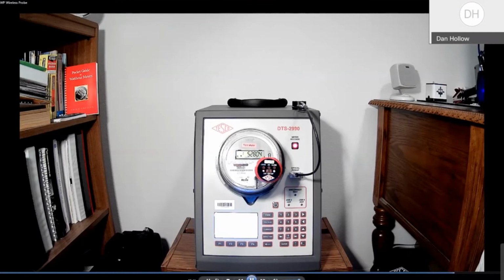And this thing will work. I have personally tested it at 300 feet. Will work up to 1,200 feet. And you can read or reprogram those meters from the comfort of your truck if you have sites where you can't get your truck within 30, maybe 50 feet, if you're talking about a Bluetooth type radio, as opposed to the radio we use. And that's it for the 1039 WP and wireless probes and why I prefer them.